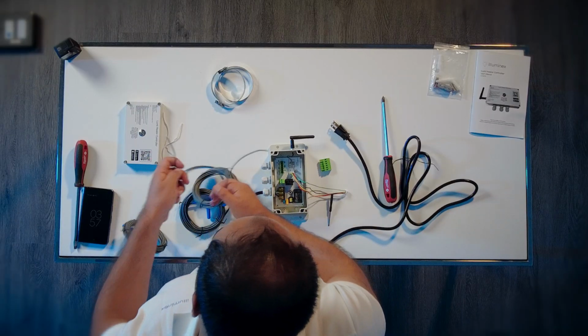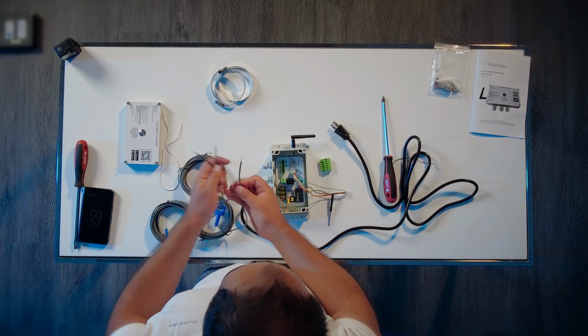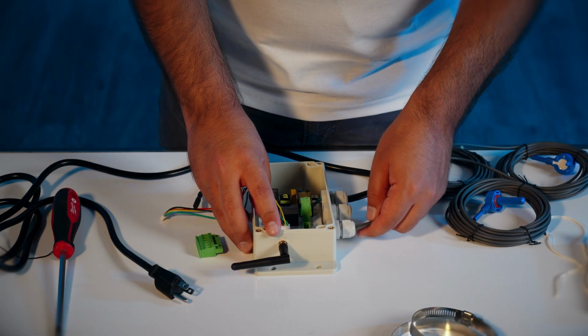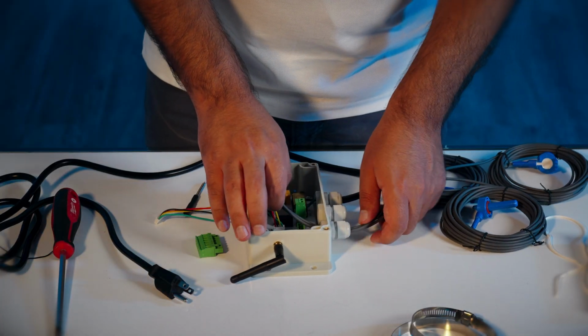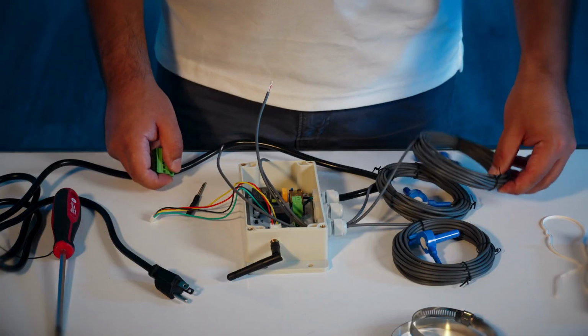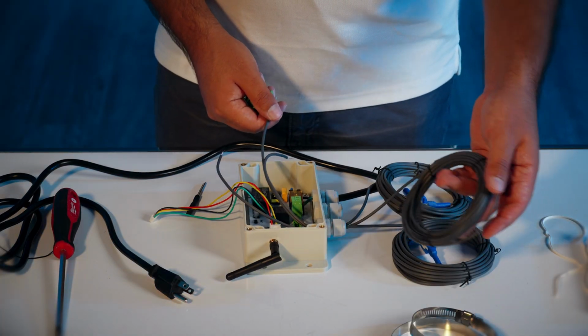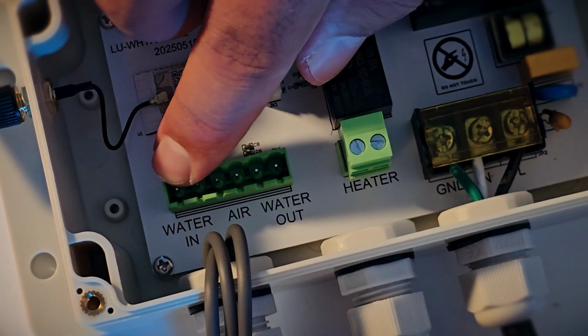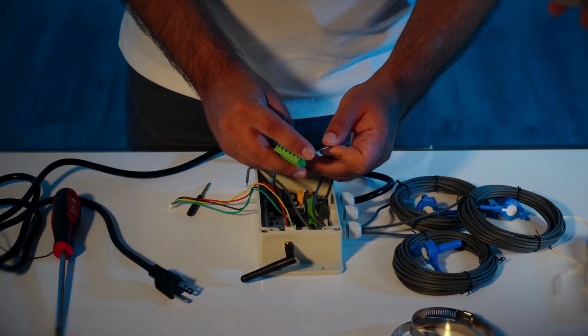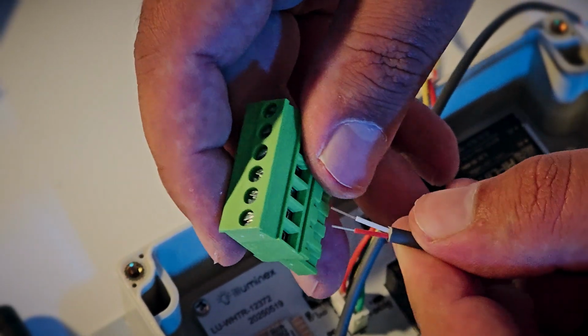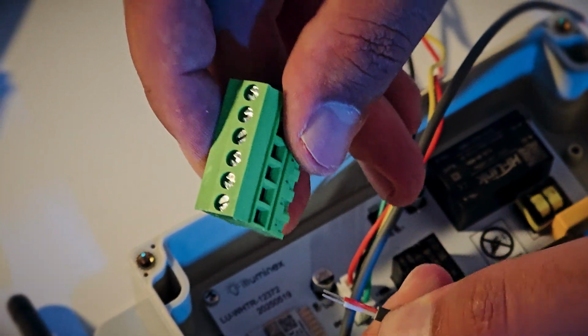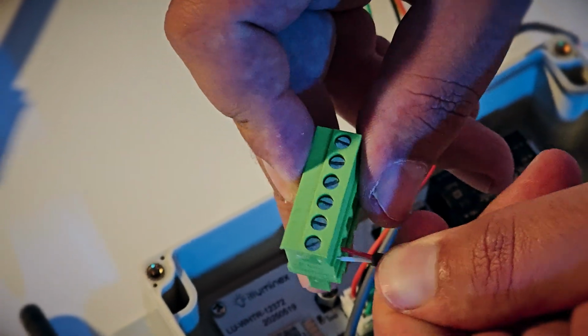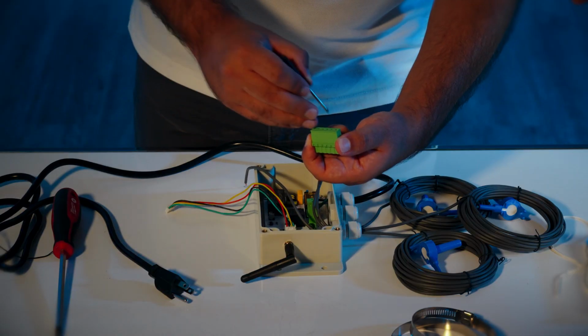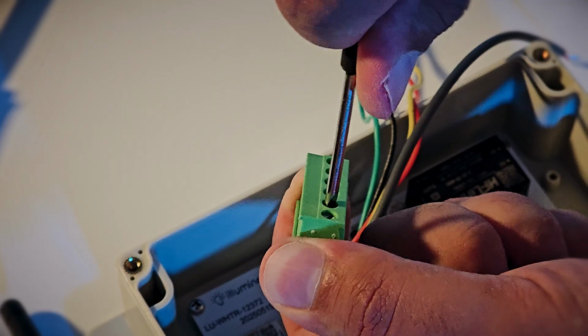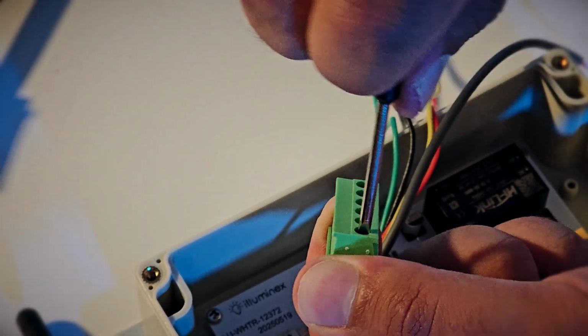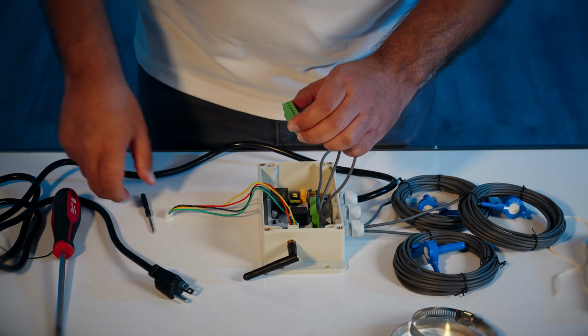Next, we're going to feed in our temperature sensors. So we're going to grab the 3 ends, feed them into the liquid tight connector. Like so. Doesn't matter which one's which, they're all the same sensor. It's up to you to decide which one you want to use where. Just make sure the water inlet is before the heater and the water outlet is after the heater. So these 2 wires are not polarity sensitive. So it doesn't matter. You can install them like this, or you can flip it over and install it in the reverse direction. Polarity is not sensitive. Once they're inside, you tighten the screw. And you move on with your next sensor.